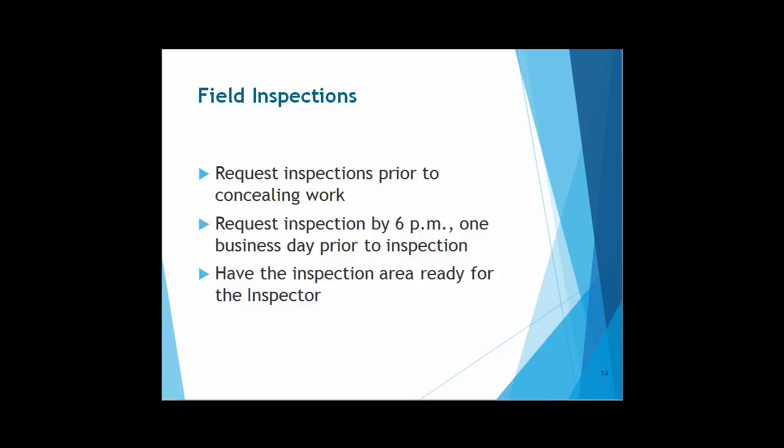We thought it would be helpful to have a brief discussion regarding field inspections. It's important that inspections are scheduled prior to any work being concealed. So in the event that a water line or sewer line was being replaced, it would be critical that the work was inspected prior to it being covered by dirt. Or if any electrical or plumbing work was being done within existing walls, that work would be inspected prior to sheetrock. It's also important that inspections are scheduled by 6 p.m. at least one business day prior to the inspection. So for a Monday inspection, the request must be made by 6 p.m. on Friday; for a Wednesday inspection, call by Tuesday at 6 p.m. It's also important to ensure that the inspection area is ready when the inspector arrives.